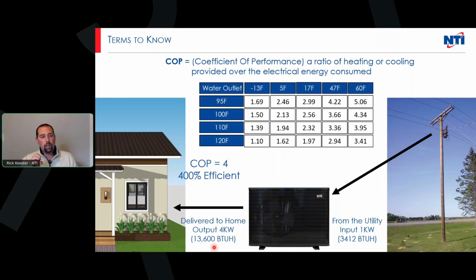Now, COP is kind of funny because it's derived at a certain condition. When we look at our charts here, and this is just a small sample for an example, if I set 17 degrees outdoor ambient temperature and I design around a 95-degree water temp, we're looking at a COP of just about 3.0 at 17 degrees. So COP is given at a certain temperature, or a certain performance level. So we're going to look at another one.